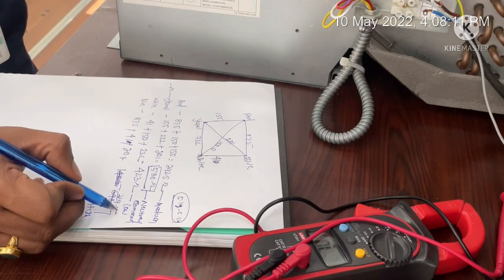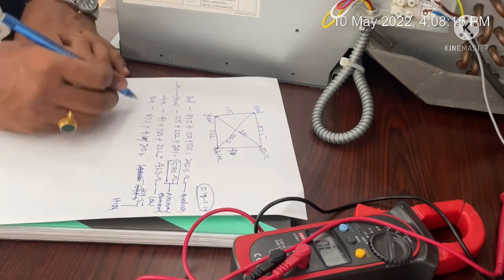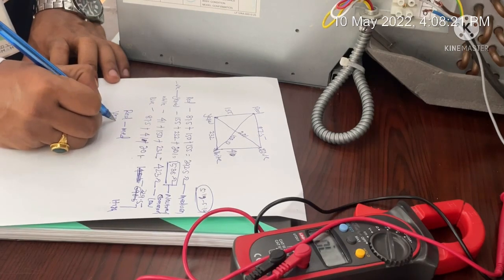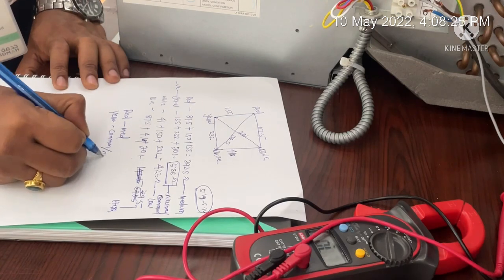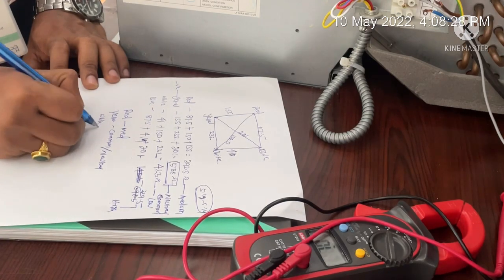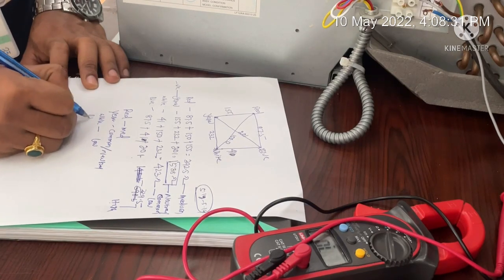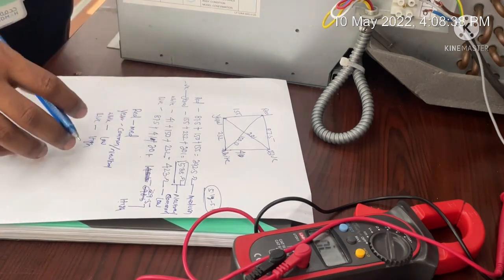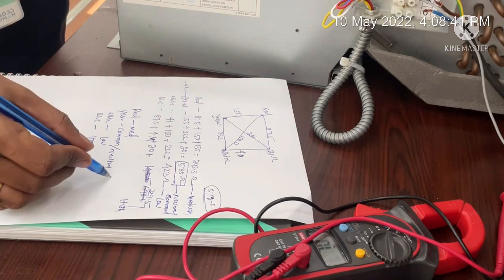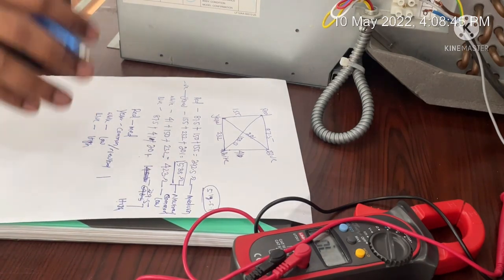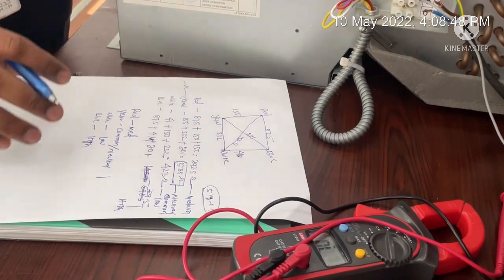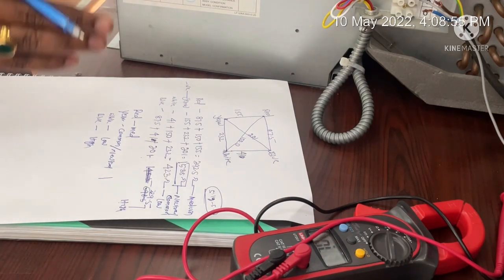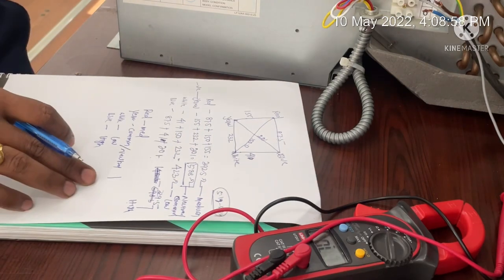As a conclusion: red will be connected with medium speed, yellow will be connected with common (neutral), white will be connected with low speed, and blue will be connected with high speed. This is how we can find out the low, medium, high, and common cable of an FCU motor. One important tip: never rely on color coding of any FCU, because if you compare a Carrier unit with SKM, the color coding is different — color coding is a trap.